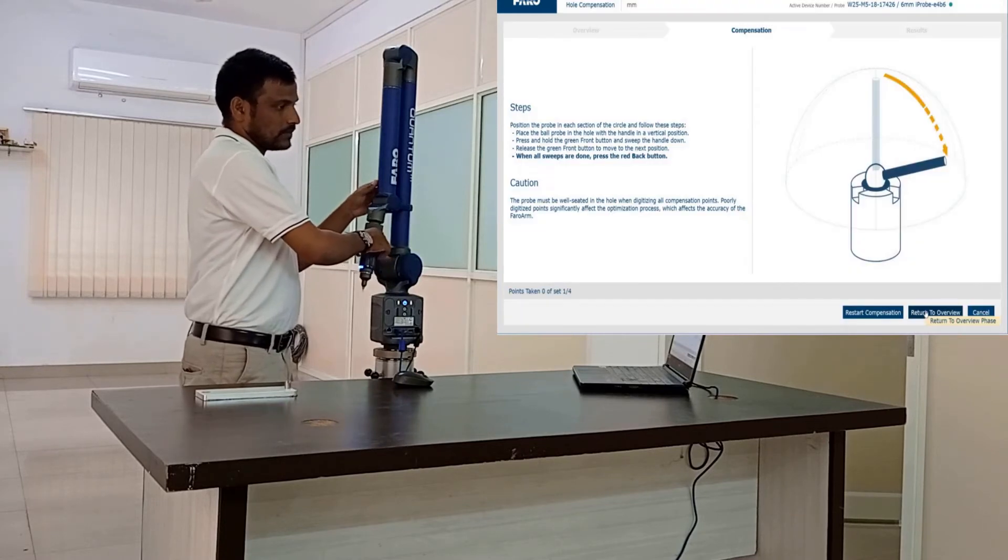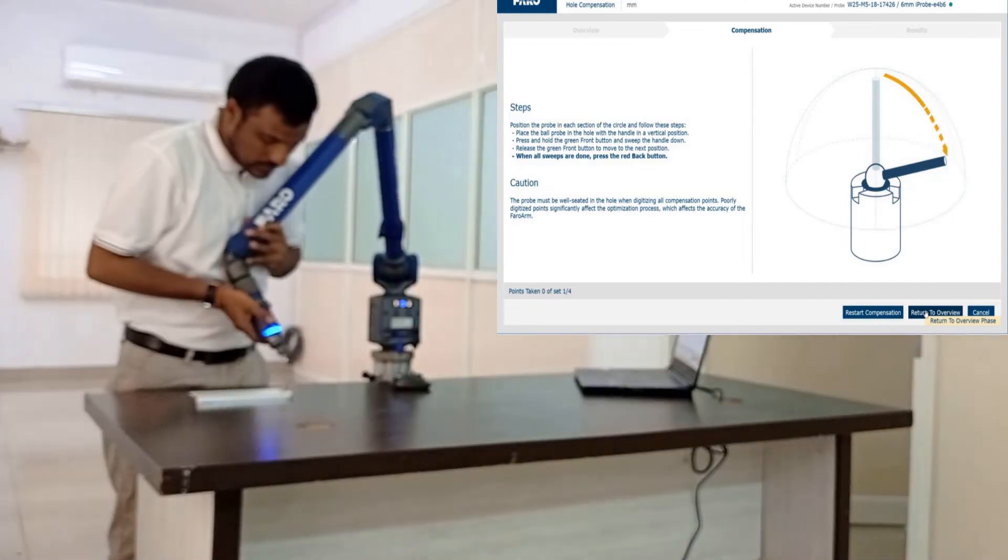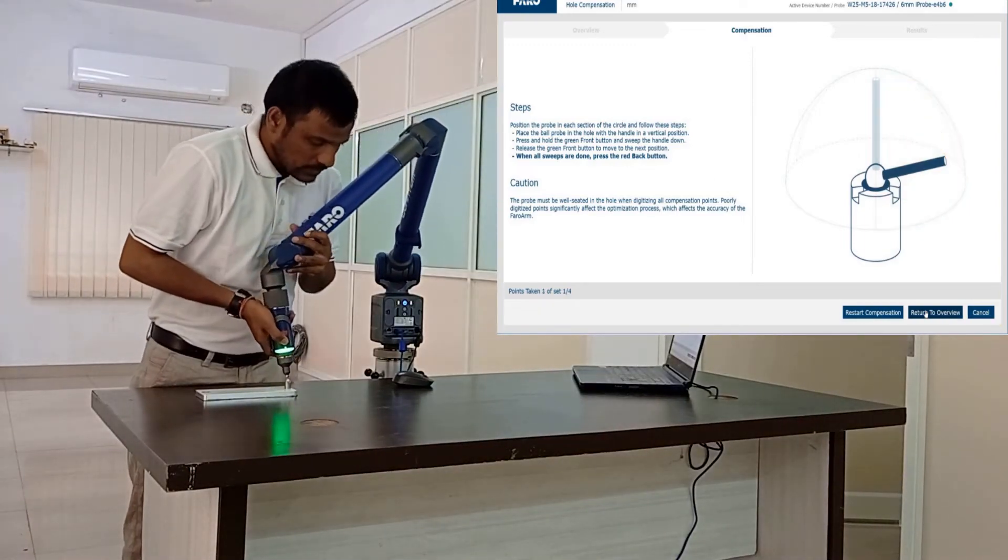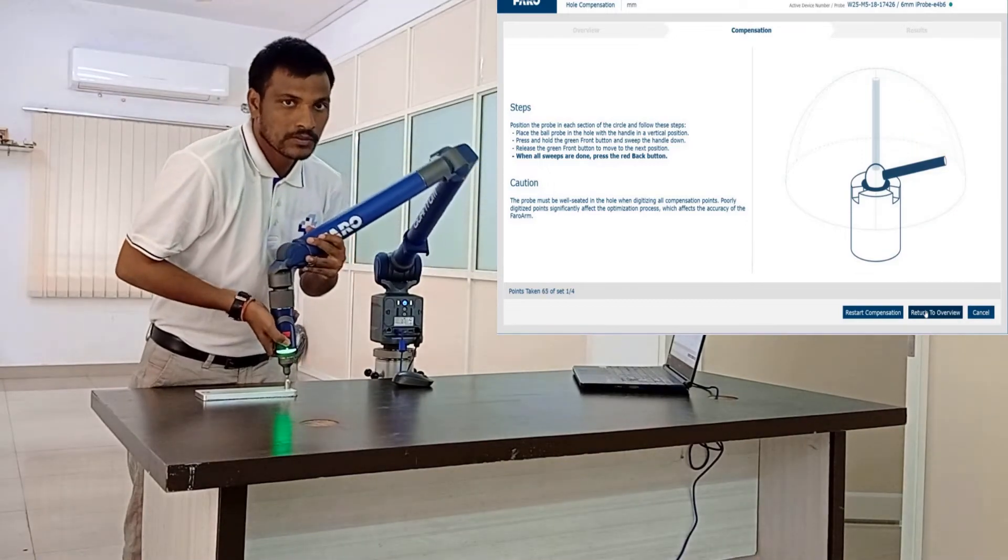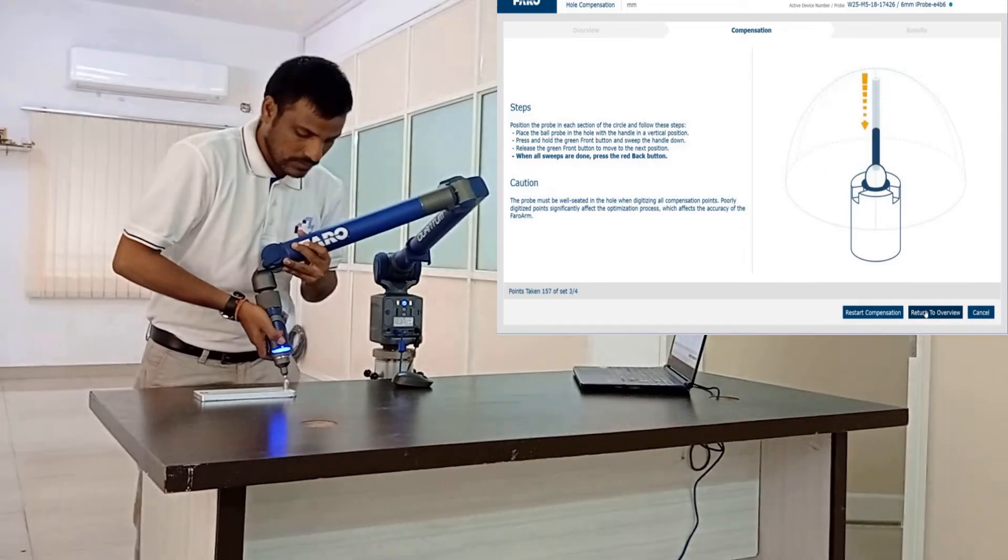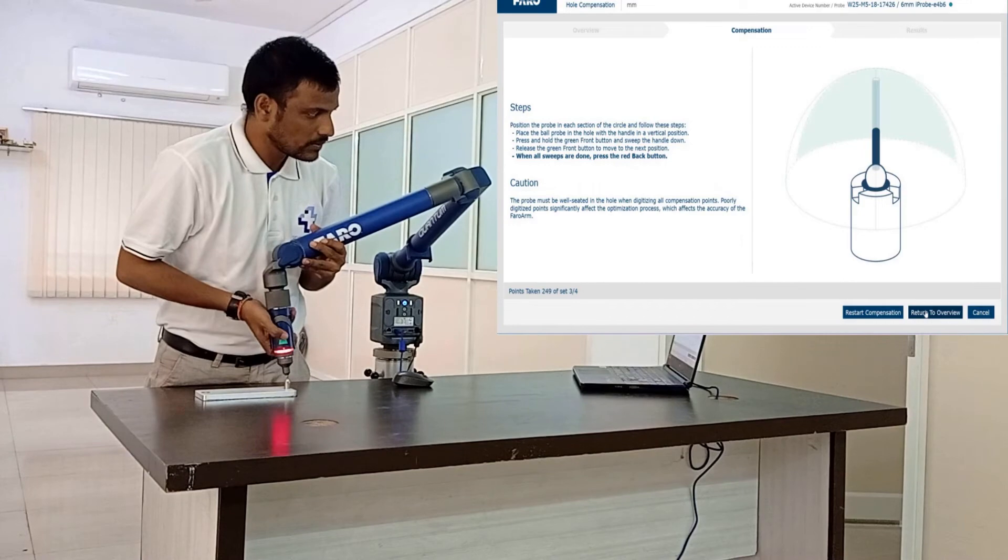First of all place the ball probe in the hole and start in a vertical position. Press and hold the green front button. Sweep to one of the horizontal positions. Ball probe has to be firmly seated in the hole. Release the green front button to move to the next position. After the three positions press red button. Place the probe in vertical position.